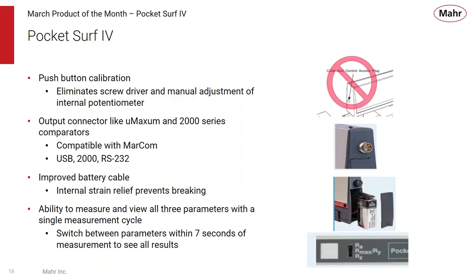We made the battery cable a little bit more robust, and inserted a strain relief that prevents breaking if being pulled on when changing the battery. And you have the ability to look at the other parameters after you've made a measurement. So you can make your measurement, look at the Ra value, and then switch the product to Rmax or Rz within 7 seconds, and you'll be able to see those values. So you don't have to measure up to 3 traces to get the 3 results. You can do that with 1. All new features for the Pocket Surf 4.